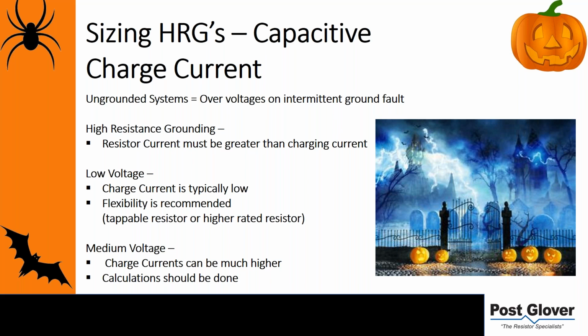So as a general rule of thumb, in my opinion—there's no real IEEE recommendation here—but I would recommend don't worry about doing an analysis at low voltage, but have some flexibility. Either a tappable resistor or a higher rated resistor. I do know that, for example, I think the PIP spec changed some of their recommendations from 5 amps to 10 amps, just to give that flexibility.